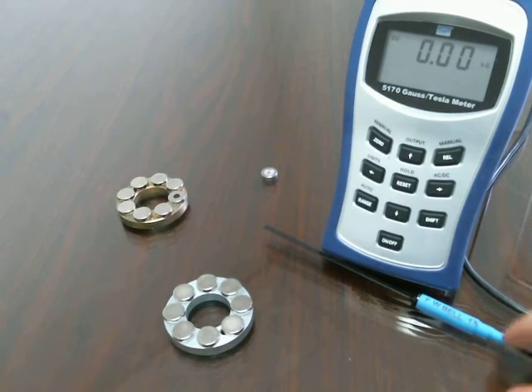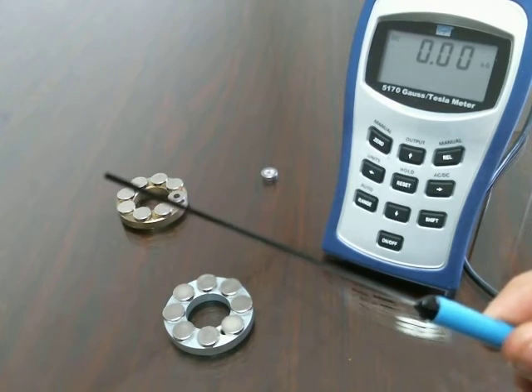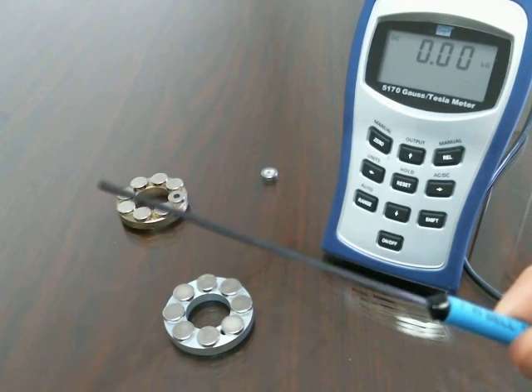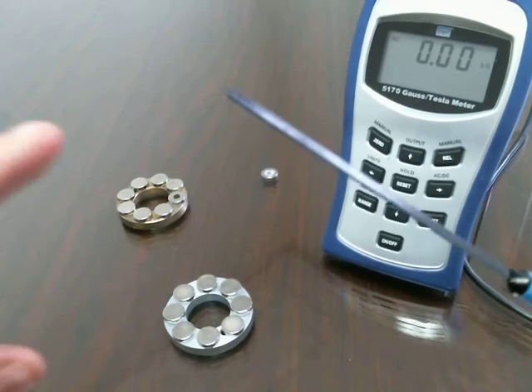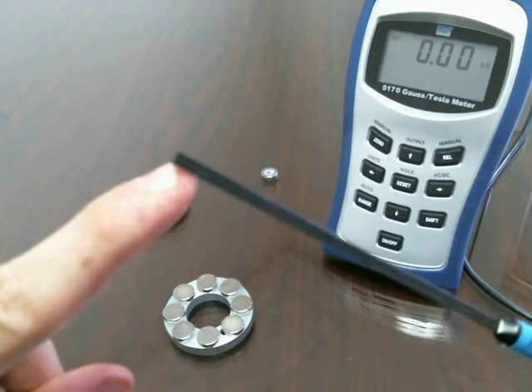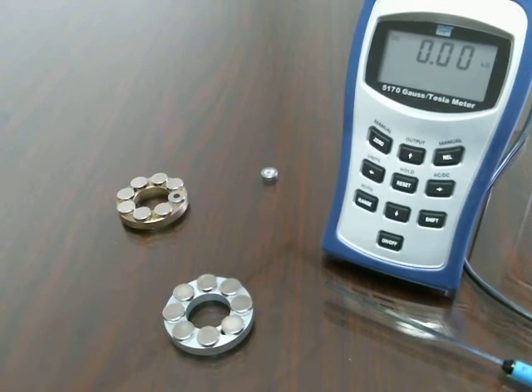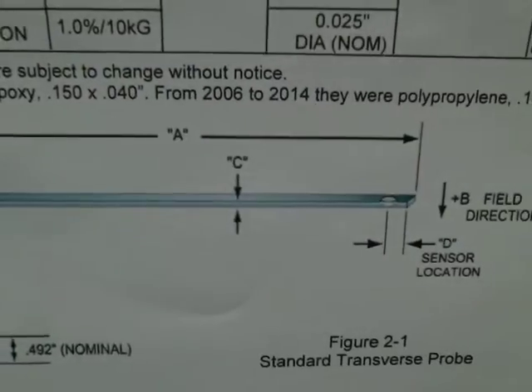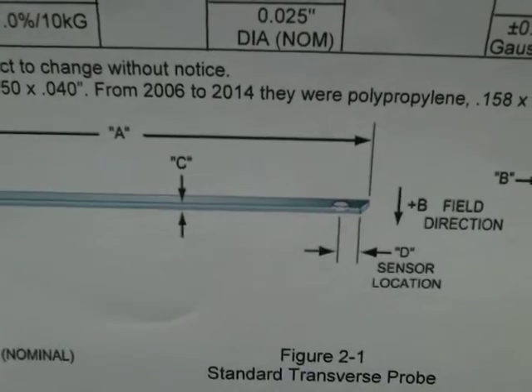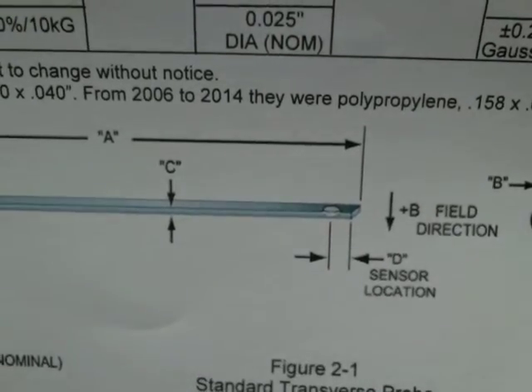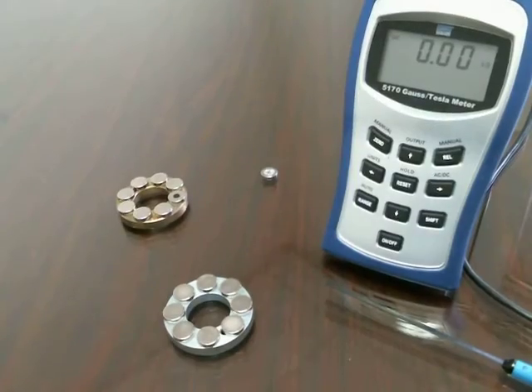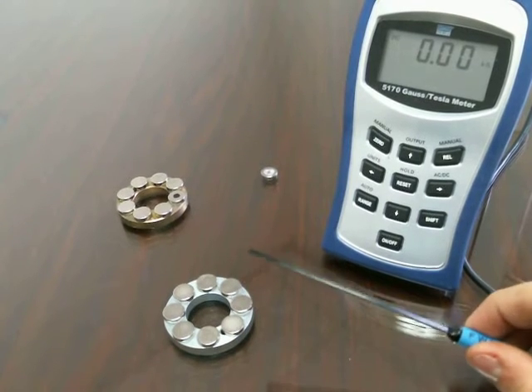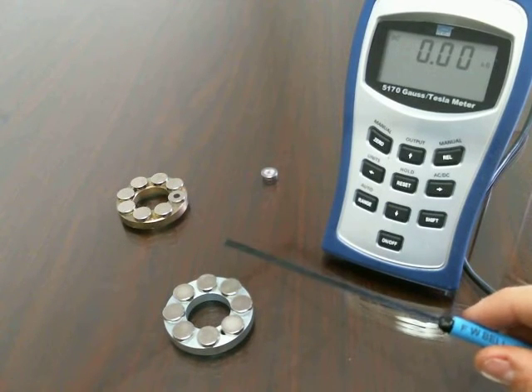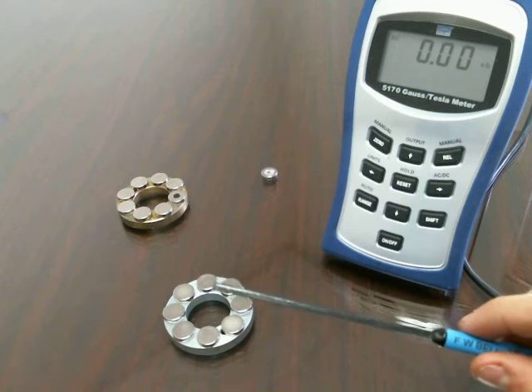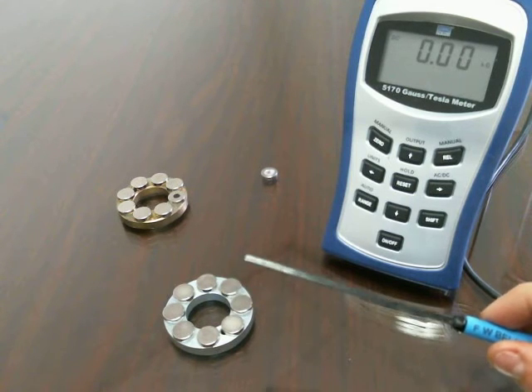First, a little bit about the Gauss meter itself. This is a transverse probe, long, flat, black probe. It's got a small sensor on the very end of this thing. Just so you can see a diagram straight from the Gauss meter catalog, that is about the relative size of the sensor in comparison to the rest of the probe. So we want to ensure that as we test these magnets, the sensor that's located within this probe is gathering all the data it can.